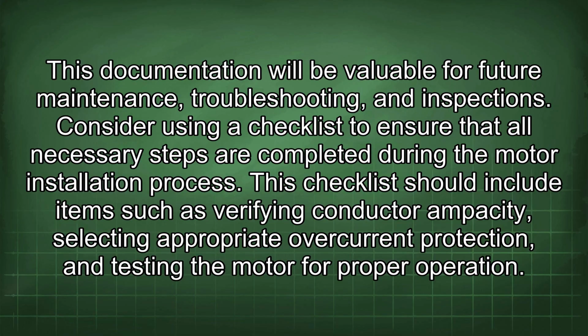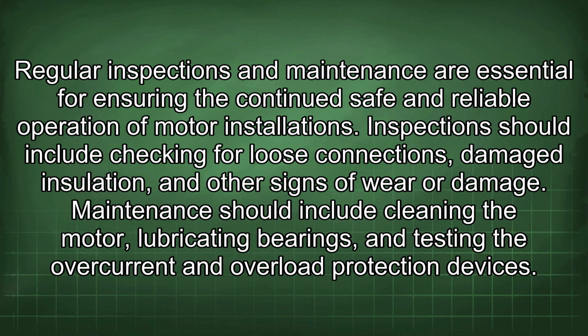Consider using a checklist to ensure that all necessary steps are completed during the motor installation process. This checklist should include items such as verifying conductor ampacity, selecting appropriate overcurrent protection, and testing the motor for proper operation. Regular inspections and maintenance are essential for ensuring the continued safe and reliable operation of motor installations. Inspections should include checking for loose connections, damaged insulation, and other signs of wear or damage. Maintenance should include cleaning the motor, lubricating bearings, and testing the overcurrent and overload protection devices.